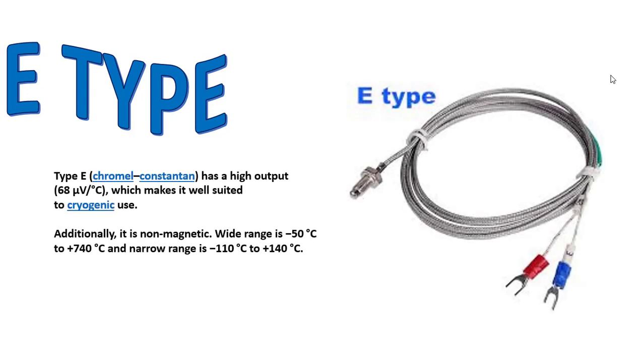Type E has high output of 68 µV per °C, which makes it well suited to cryogenic use. Additionally, it is non-magnetic with a wide range of -50°C to +740°C and narrow range of -110°C to +140°C.